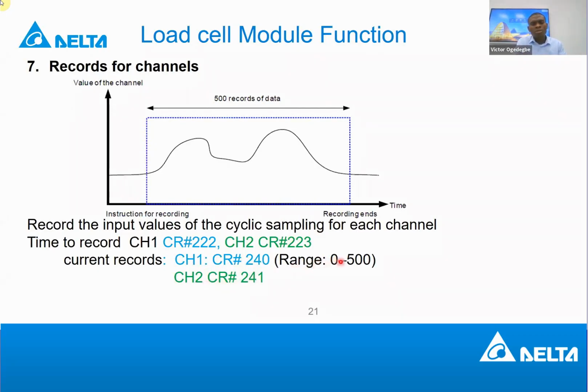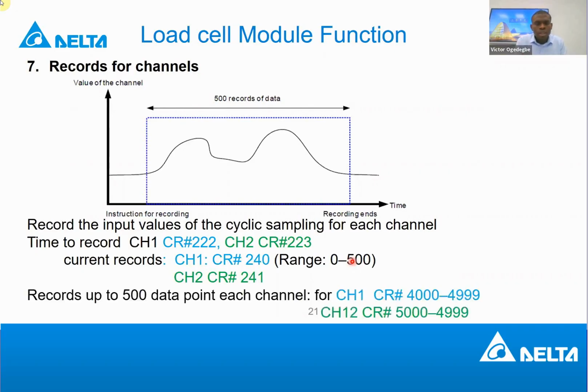And then the range: you can record a maximum of 500 records. So I believe when 500 records are made, any new record will be overwritten. If you need the 500 and you don't want them overwritten, it's good that after a time you retrieve those data, and maybe plot a graph with them. Otherwise, since only 500 can be recorded, once the stack is full, like in the HMI, you can control it to stop or to continue, and then the stack will be overwritten. So what was recorded yesterday, you cannot see today, because new ones fill the memory. That is the record for channels.